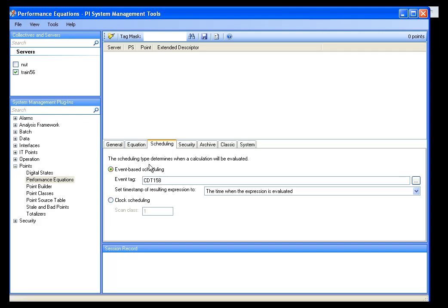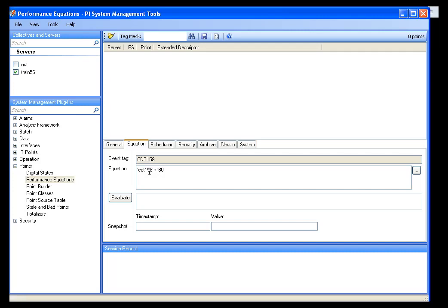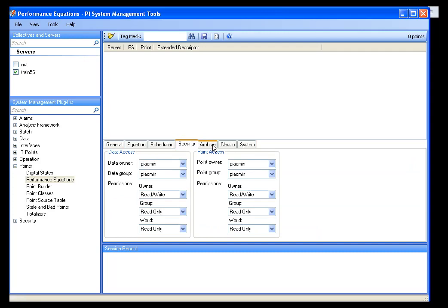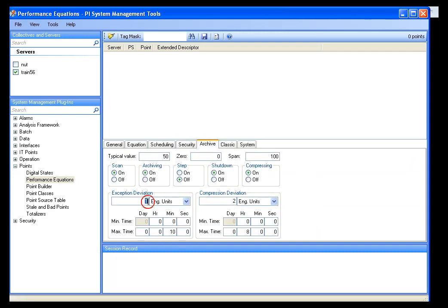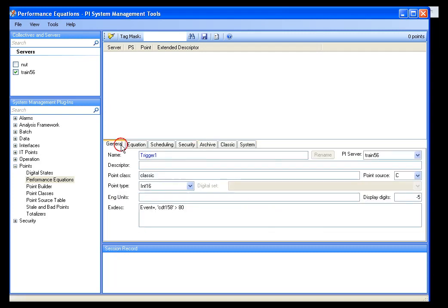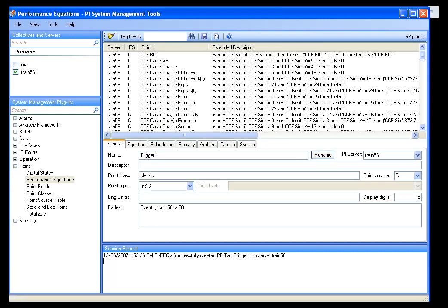Every time CDT158 gets a value, I'm going to evaluate this expression. And if it's greater than 80, then I want my batch to start. It works out very well that it's going to report a 0 or a 1 — true or false. In this case, I don't want to miss any of my threshold events, so I'm going to set my deviation to 0 for both exception and compression, because I want to make sure I keep all of the results from my expression and equation tag. I'll save this, and now this tag can be used to generate certain values for my triggers.